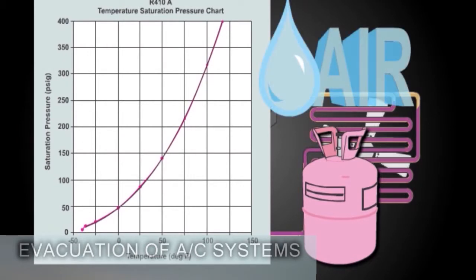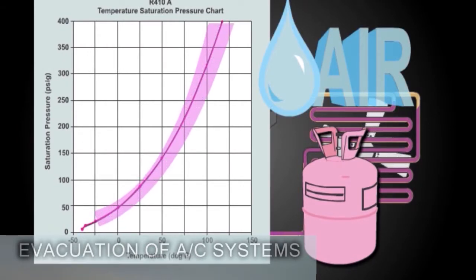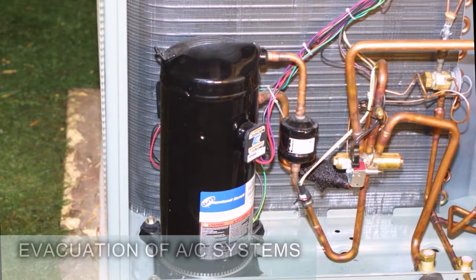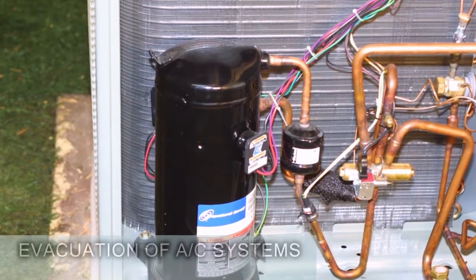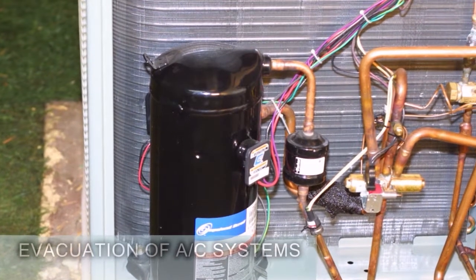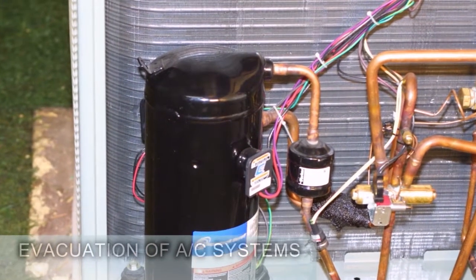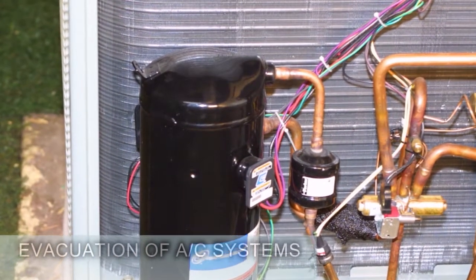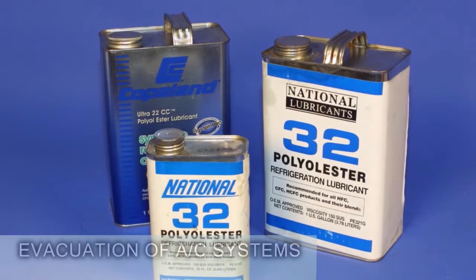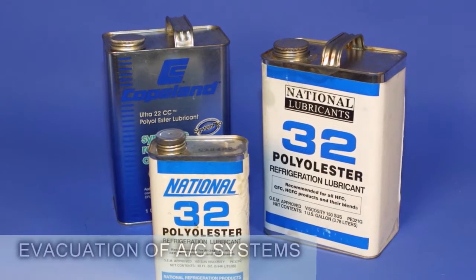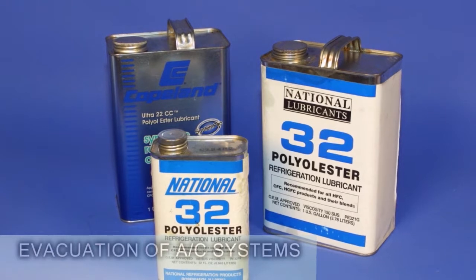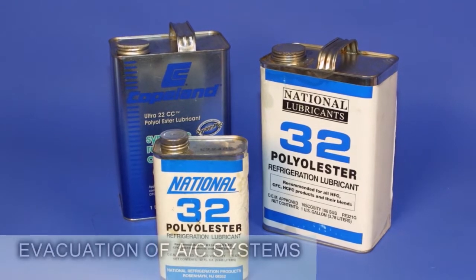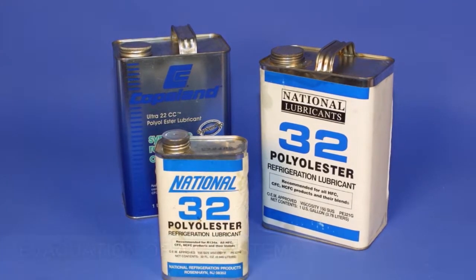The moisture remaining in an operating system does more than change the operating performance on the refrigerant circuit. Moisture mixed with oil in the shell of a compressor weakens the lubrication ability of the oil, leading to higher friction and shorter life for the compressor. Loss of lubrication ability of an oil from moisture absorption is even worse if the oil is a POE type oil typically used with 410A refrigerant.